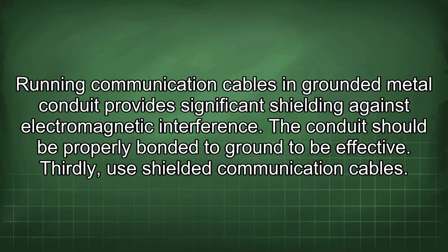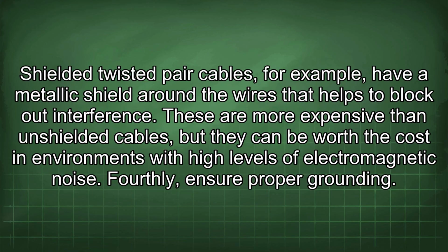Thirdly, use shielded communication cables. Shielded twisted pair cables, for example, have a metallic shield around the wires that helps to block out interference. These are more expensive than unshielded cables, but they can be worth the cost in environments with high levels of electromagnetic noise. Fourthly, ensure proper grounding.